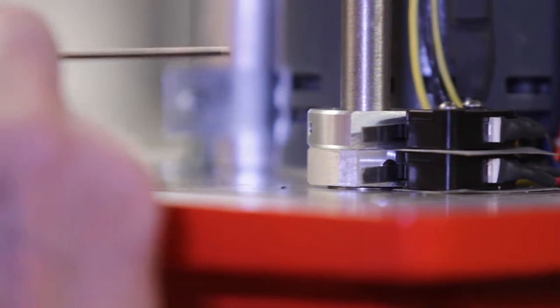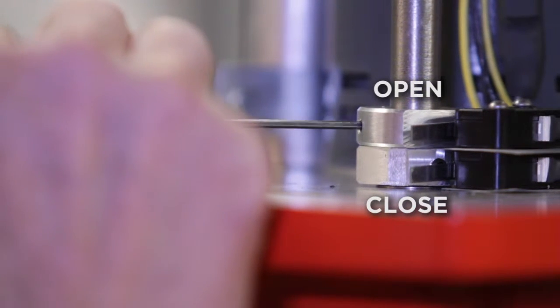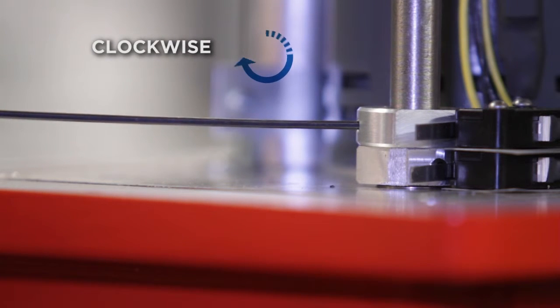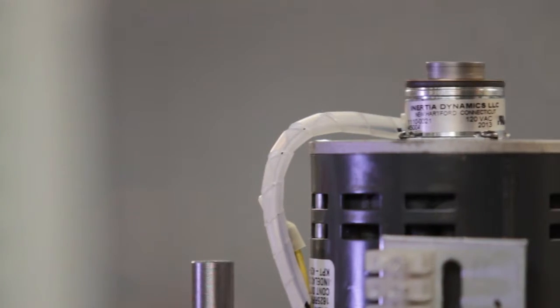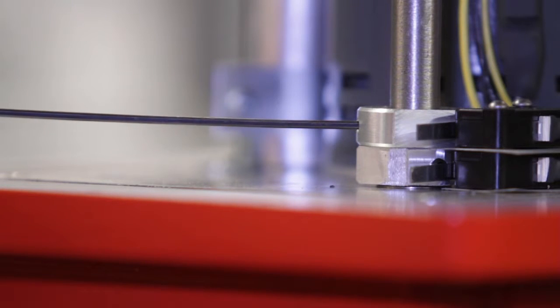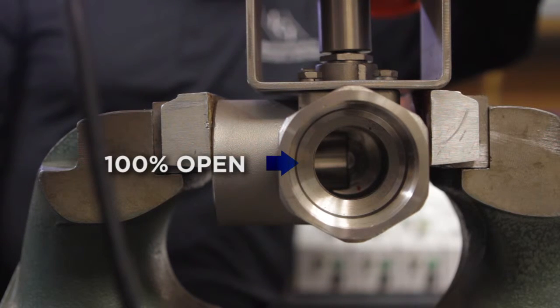Using the 5/64 inch Allen wrench, loosen the set screw securing the top cam to the motor shaft. Rotate the cam clockwise slightly. The motor will now begin to run. By making small incremental adjustments to the cam, you will be able to position the actuator exactly where you want it.